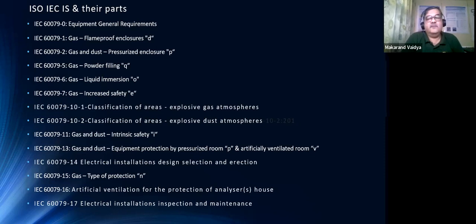What is flame proof? What is X-proof? Usually we deal with what we know as a junction box, which looks like some aluminum casting. By the way, it is not actually aluminum, it is LM6, an aluminum alloy. Aluminum itself is not acceptable in flame proof areas. LM6's ingredients include some percentage of silica and copper.